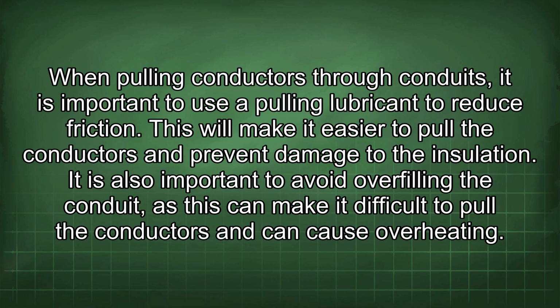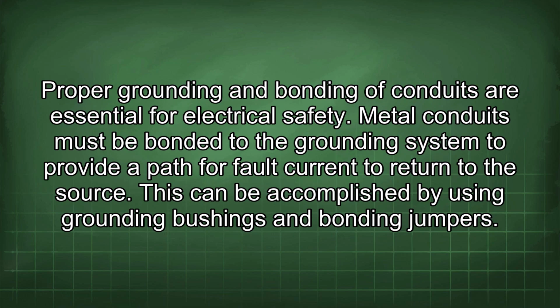This will make it easier to pull the conductors and prevent damage to the insulation. It is also important to avoid overfilling the conduit, as this can make it difficult to pull the conductors and can cause overheating. Proper grounding and bonding of conduits are essential for electrical safety. Metal conduits must be bonded to the grounding system to provide a path for fault current to return to the source. This can be accomplished by using grounding bushings and bonding jumpers.